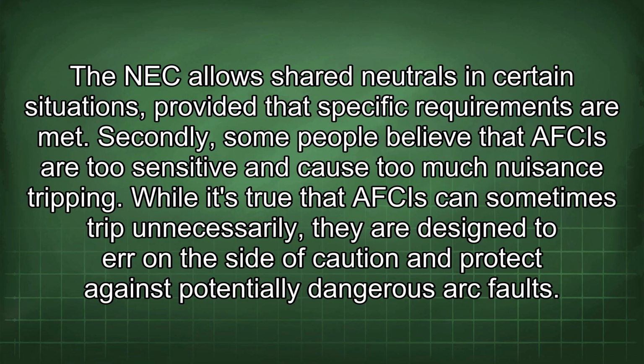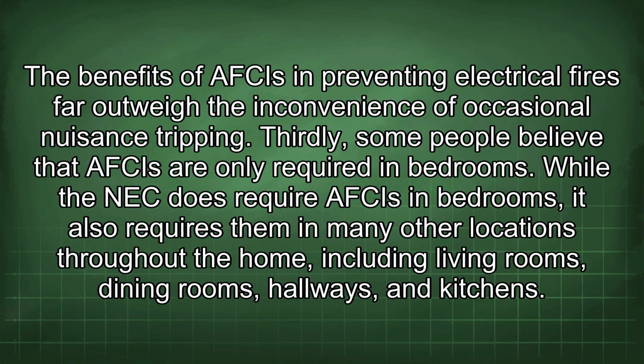Secondly, some people believe that AFCIs are too sensitive and cause too much nuisance tripping. While it's true that AFCIs can sometimes trip unnecessarily, they are designed to err on the side of caution and protect against potentially dangerous arc faults. The benefits of AFCIs in preventing electrical fires far outweigh the inconvenience of occasional nuisance tripping.